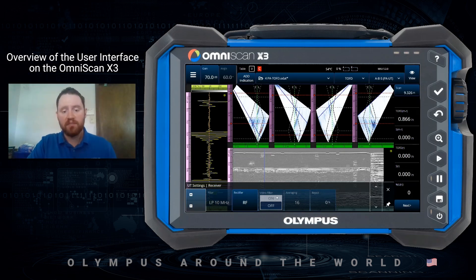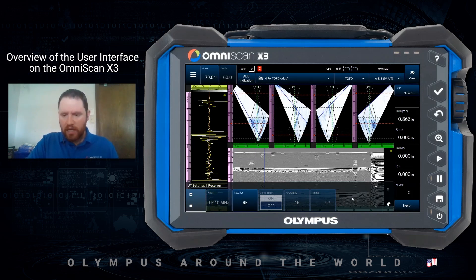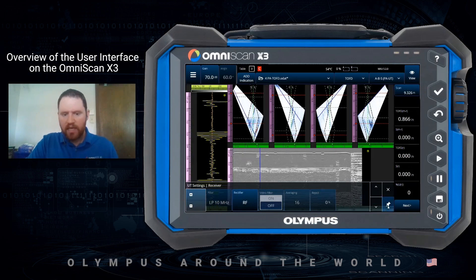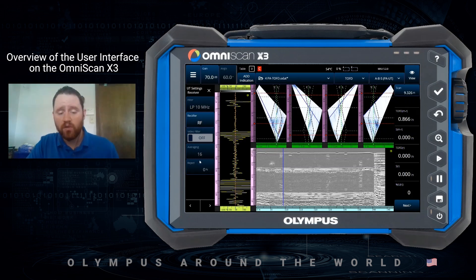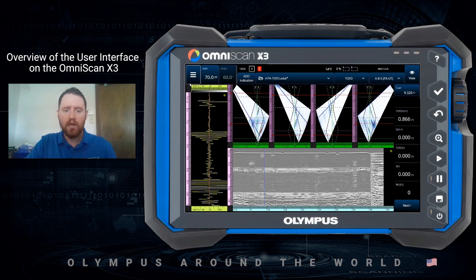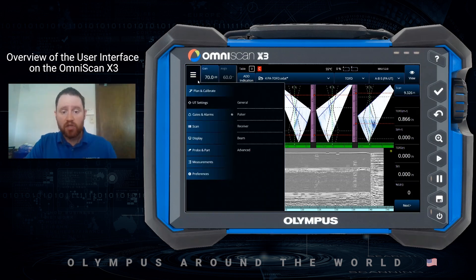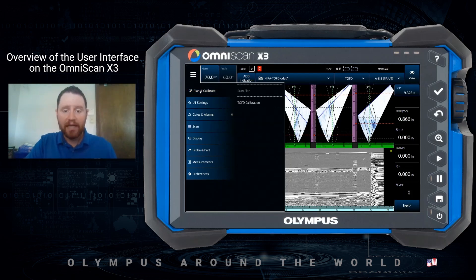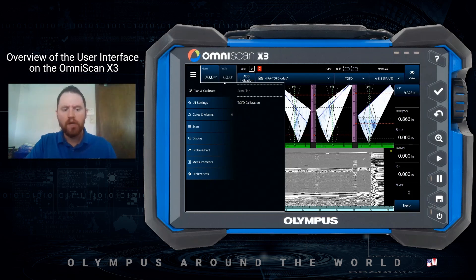A lot of OmniScan users are accustomed to having these parameters and sub-menus across the side and along the bottom of the display. With the pin icon, we can toggle those menus to the left-hand side. If your preference is to have those there, you can place them on the left-hand side with that pin. If I want to maintain a large viewing area for the data, I can click the X icon and remove those menus from the screen. We'll have other videos that will show examples of going through various setups.